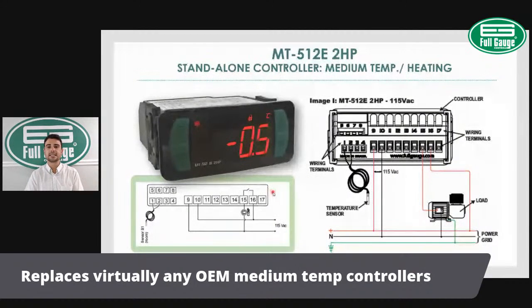But let us look at this particular case, where we have the compressor in 110 and the controller in 110. How do you wire the controller in 110 to control a 110 compressor? We have neutral and hot line going into terminals 9 and 10. That is feeding power to the controller. Now, we have to bring that hot line from terminal 10 into terminal 16. That means we are energizing the relay circuit. So you are feeding power to the relay circuit so it can control the compressor in 110 volts.